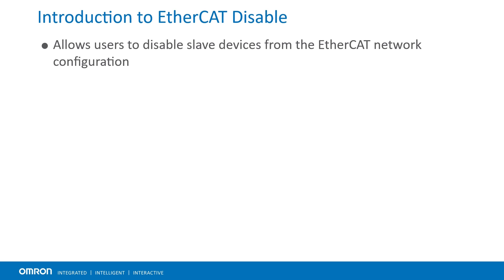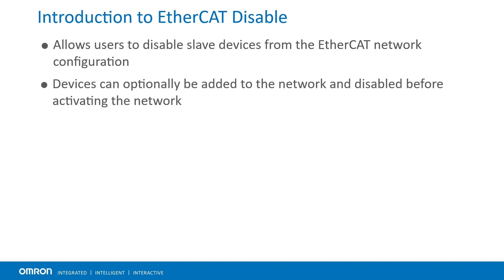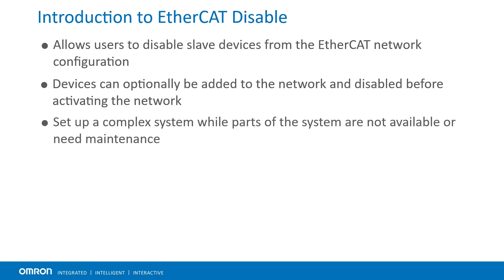The EtherCAT disable feature is designed to disable slave devices in the active configuration without affecting overall functionality. It is often required to operate the system without a perfect match between the EtherCAT bus configuration and the actively connected devices. Using the disable function, devices can optionally be added to the network and disabled during operation without causing an error on the EtherCAT network. This functionality makes it possible to set up a complex system while parts of the system are not available or need maintenance.